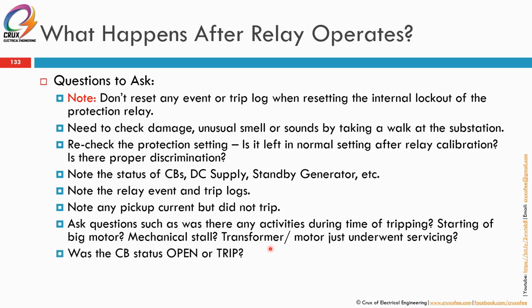And last question is that people normally forget to differentiate whether the CB, the circuit breaker status, is in open or tripping condition. If you ask non-electrical people, open or tripping is the same. But if you ask electrical, open or trip is very much different from one another. Because open, normally we refer to the open condition as when we want to open the breaker, like that. But trip is due to a tripping, due to overcurrent, due to a fault, overload. Okay.